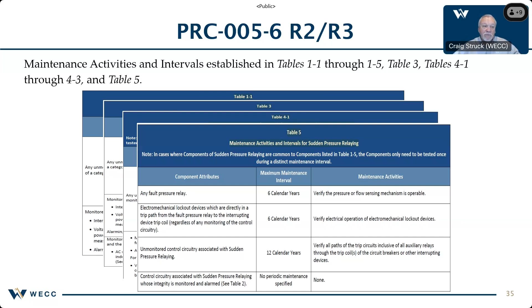The first row in the first column indicates the component attribute to be any fault pressure relay. This is referring to the relay itself and not any other component attributes such as control circuitry. Moving to the right, you'll notice that 6 calendar years is the maximum maintenance interval allowed. And moving to the right yet again, you'll notice the maintenance activity is to verify pressure or flow sensing mechanism is operable. Again, this was just to give you a basic feel for how the tables within the standard are arranged. Next slide, please.